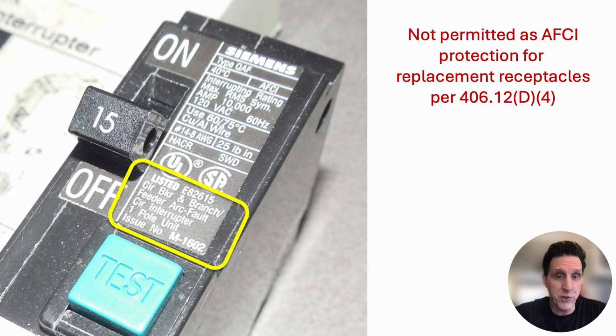It's not a combination AFCI. So right now, the way it's worded presently and apparently in 2026, you're still not going to be able to use this particular type of AFCI breaker to provide AFCI protection when you're replacing a receptacle.